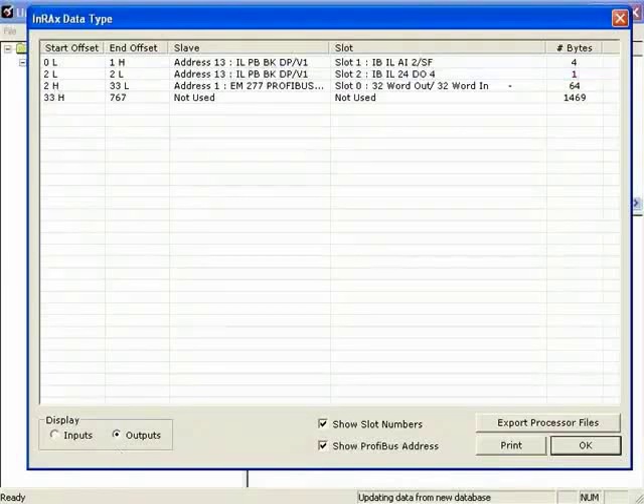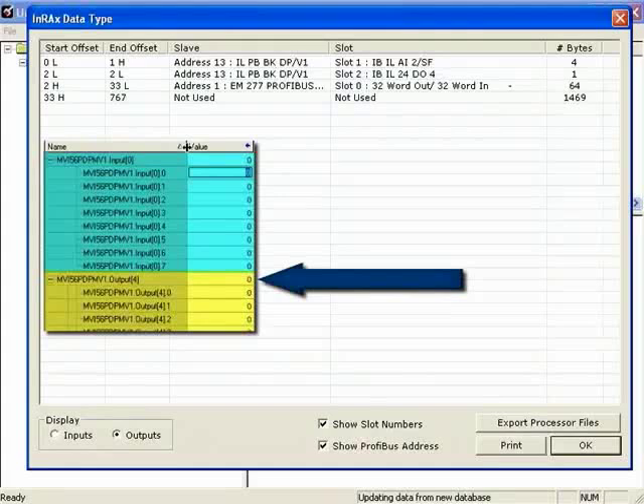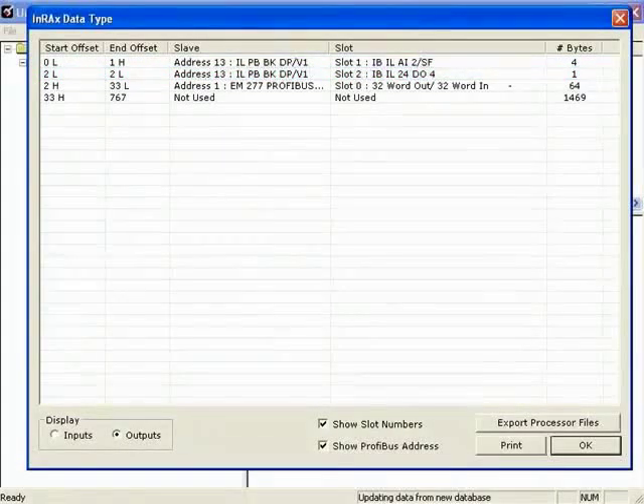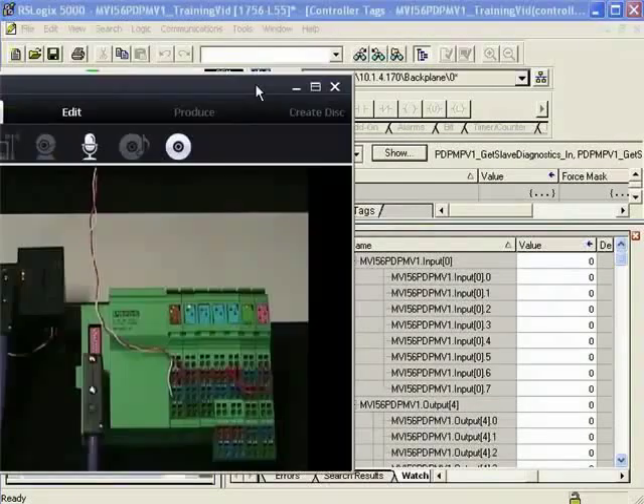To summarize: our controller tags are in bytes, so byte number 4 in our controller tags is mapped to Word number 2 of our Profibus network, and Word 2 is mapped to our digital output module. Now I'm going to bring in the help of a video monitor and monitor the I/O as we toggle some bits. On the left we have the Profibus DP bus terminal, and just to the right of that we have the IL DI 8, the inline 8-channel digital input module. Then to the right is the 2-channel analog input module, and lastly the DO4, the 4-channel digital output module.